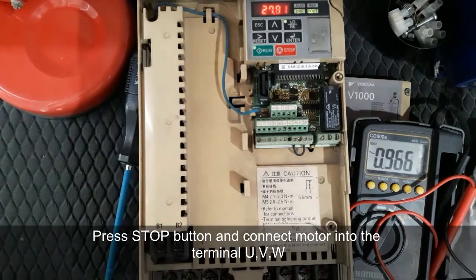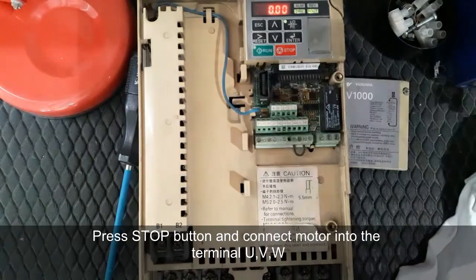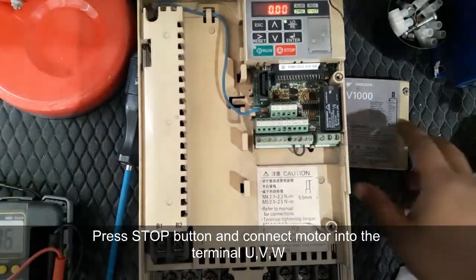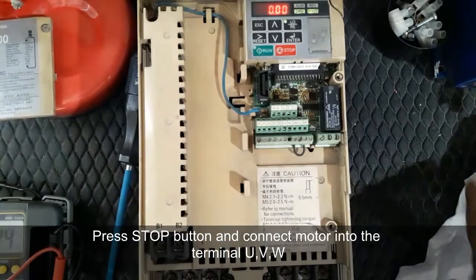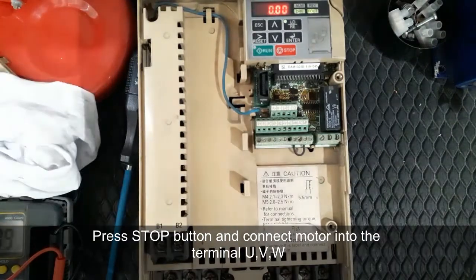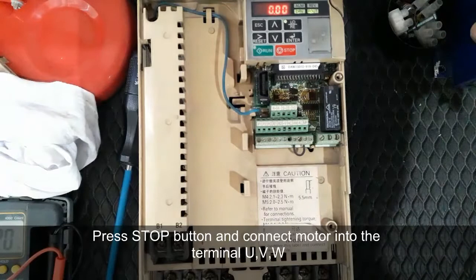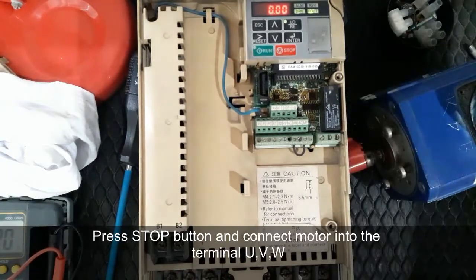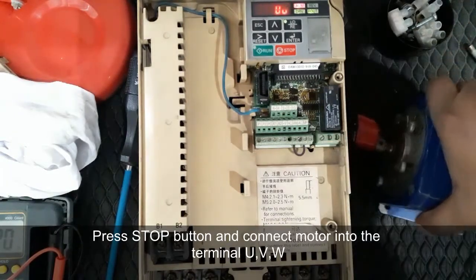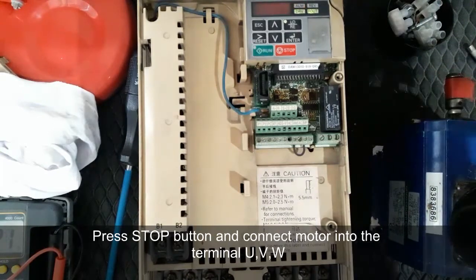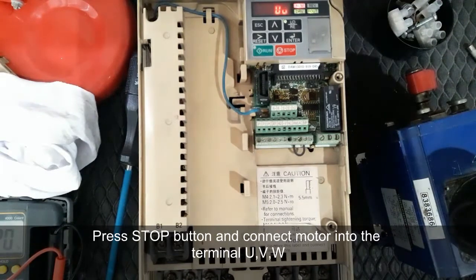Connect a motor to the terminals U, V, W to drive the motor by this inverter. So we use a screwdriver to set the motor connection into the terminals. Here we are using a small induction motor for testing output. We will check the motor speed driven by the inverter at 2 Hz frequency and 50 Hz frequency.